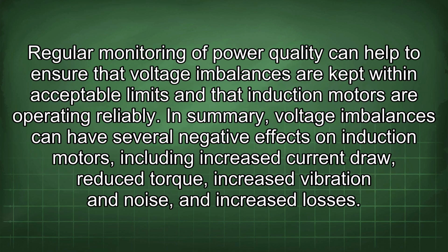Regular monitoring of power quality can help to ensure that voltage imbalances are kept within acceptable limits and that induction motors are operating reliably. In summary, voltage imbalances can have several negative effects on induction motors, including increased current draw, reduced torque, increased vibration and noise, and increased losses.